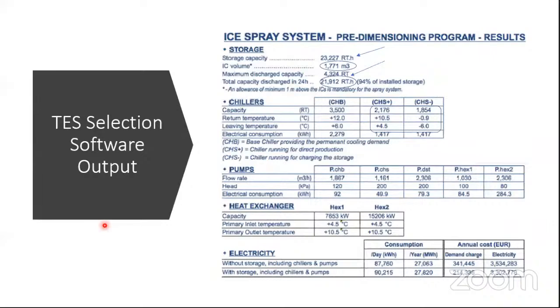This is additional output, like the storage capacity, the total thermal storage capacity. It works this out, and this is for ice capsules, and what should be the total volume. Based on total volume, you can calculate the tank volume also, and what is the maximum discharge capacity. So this is our peak load on thermal storage, so we can plan our pump flow rate also, although it is done automatically in the software itself, but we can do it manually also.